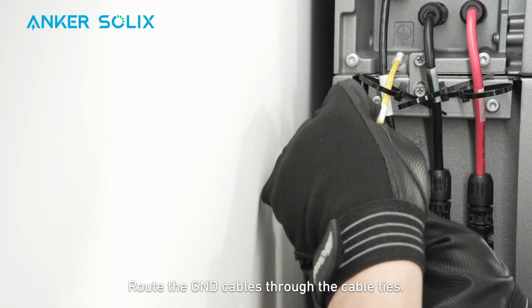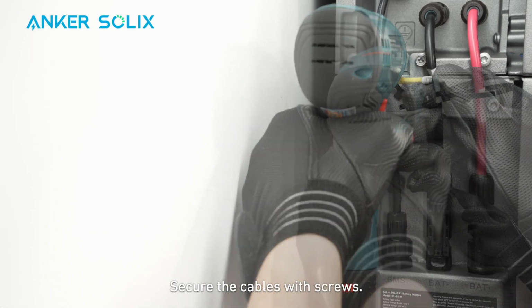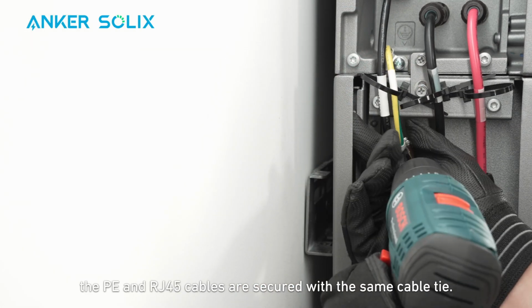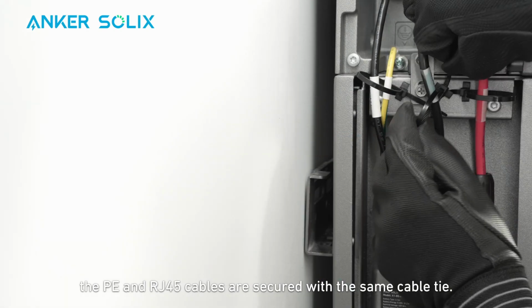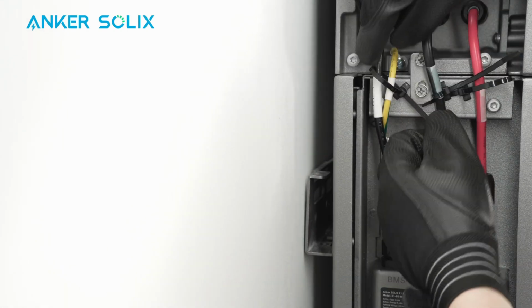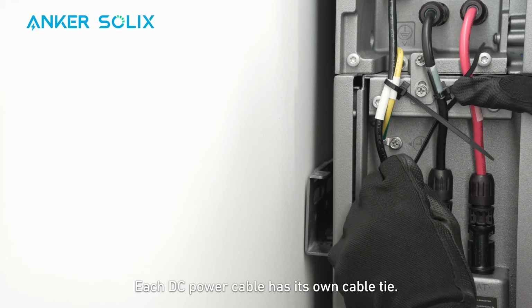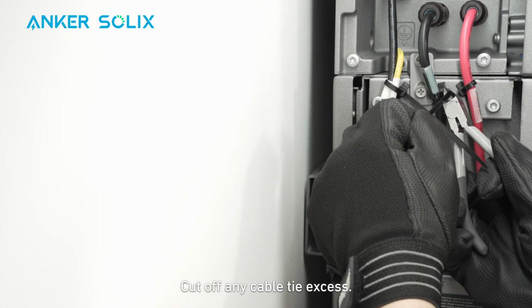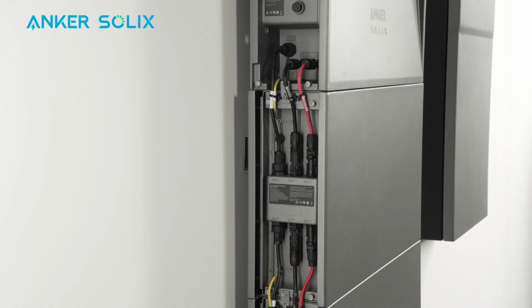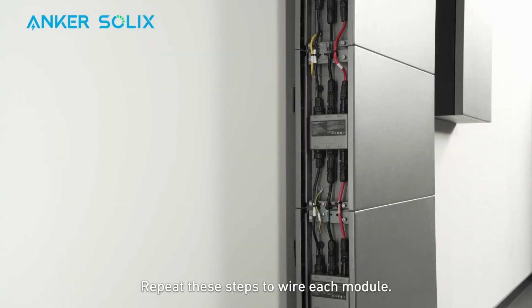Route the ground cables through the cable ties. Secure the cables with screws. Just a reminder, the PE and RJ45 cables are secured with the same cable tie. Each DC power cable has its own cable tie. Cut off any cable tie excess. Repeat these steps to wire each module.